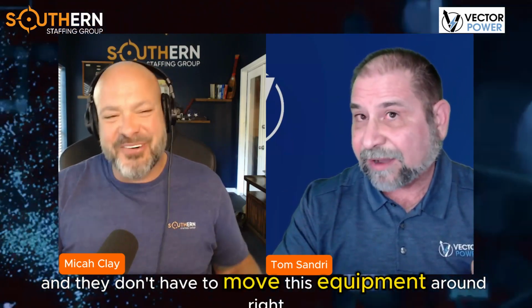So you have what I'll call the factory world of testing. And as you can imagine, in the factory world of testing, they don't have as many of the obstacles that we face in the field. Generally speaking, almost all of their testing is traditionally done at power frequency, 50 or 60 hertz. The size, weight, and construction of the power supplies needed to energize these cables to the recommended voltage levels is not a hindrance to them at 60 hertz. They've got the real estate and the room, and they don't have to move this equipment around. It's not like two technicians are going to pick it up at the end of the day, fit it in the back of their truck, and haul it to the next job. It's going to stay in place. So they get to operate in a very controlled environment, under very controlled conditions.